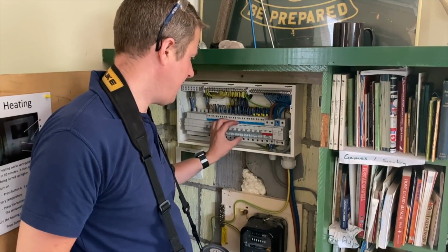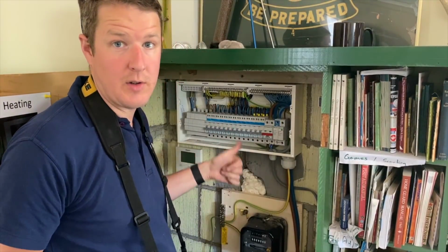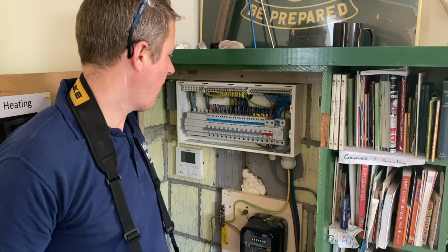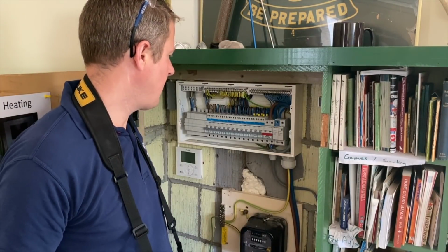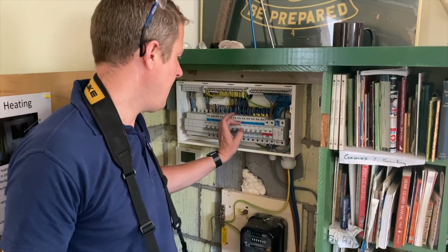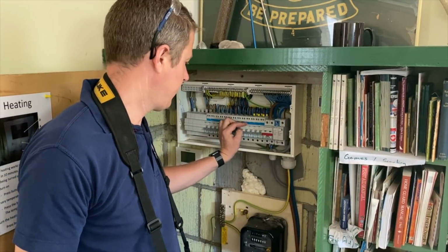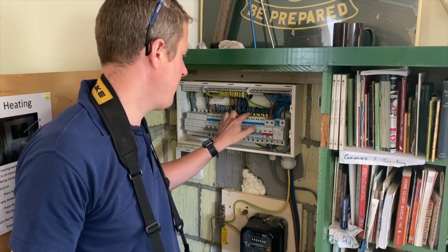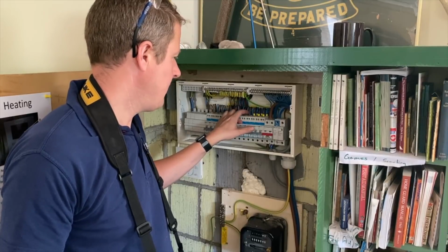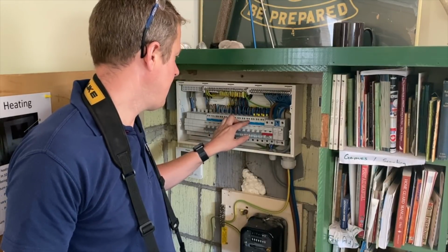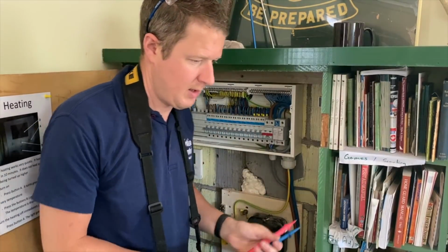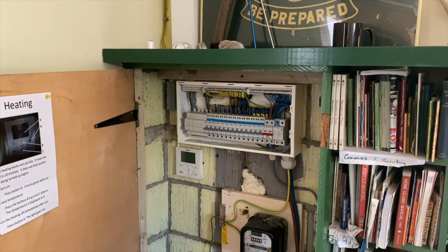Right, so that is insulation resistance done, continuity of CPCs done. So the next test that we do is continuity of ring final circuits. In this case, we've only got one ring final circuit, which is this one, 32 amp. We've got 2 cables in there. So we've just got to disconnect these and disconnect the earths and then do a continuity test to make sure we do have ring continuity.